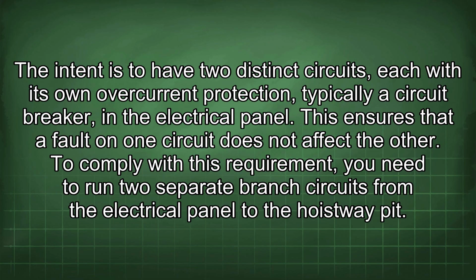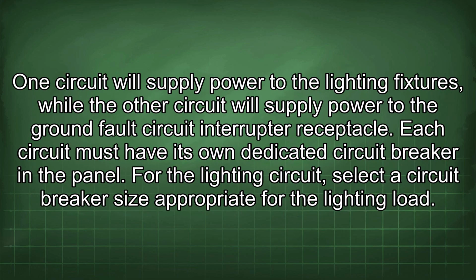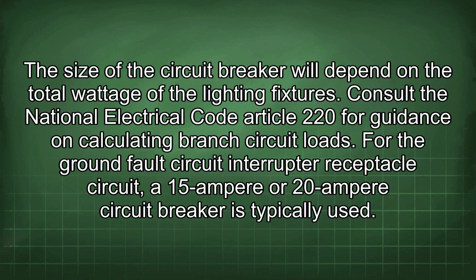To comply with this requirement, you need to run two separate branch circuits from the electrical panel to the hoistway pit. One circuit will supply power to the lighting fixtures, while the other circuit will supply power to the ground fault circuit interrupter receptacle. Each circuit must have its own dedicated circuit breaker in the panel. For the lighting circuit, select a circuit breaker size appropriate for the lighting load. The size of the circuit breaker will depend on the total wattage of the lighting fixtures. Consult the National Electrical Code Article 220 for guidance on calculating branch circuit loads.